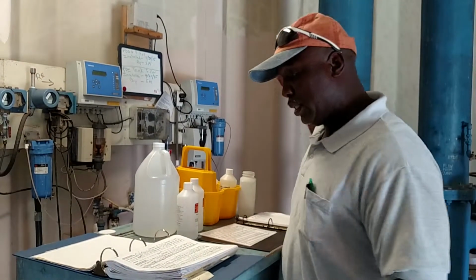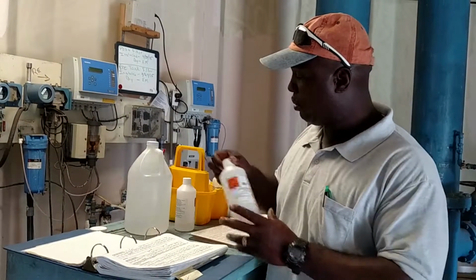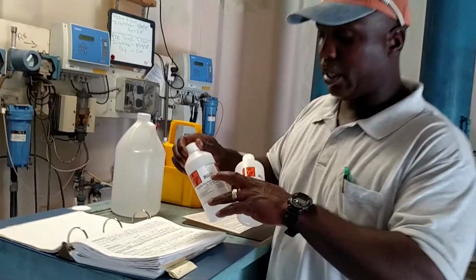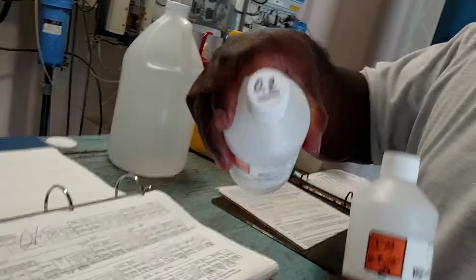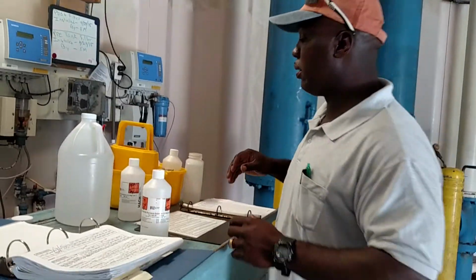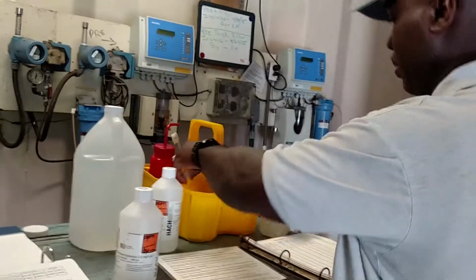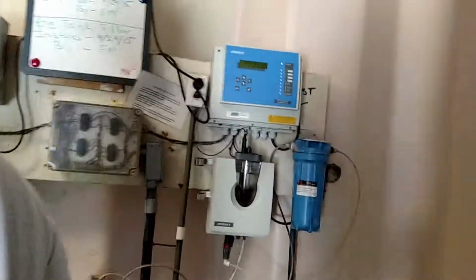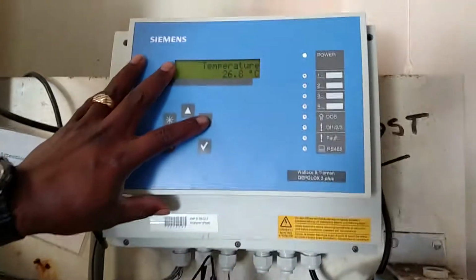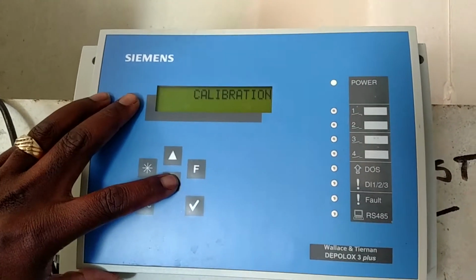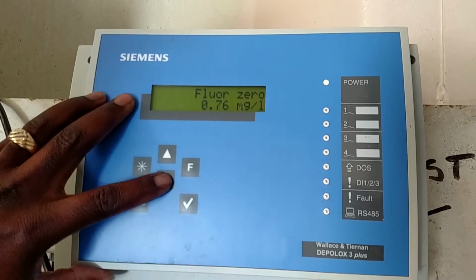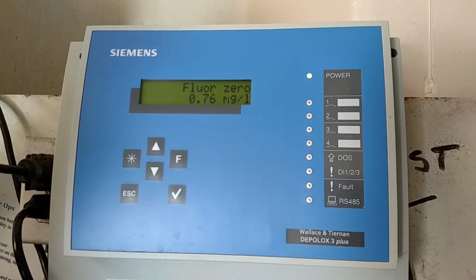Right now it's 0.76, and then I record the temperature from off of the analyzer. Then each one of my standards have a lot number on there. I record the lot number, and I record also the expiration date. And this is 0.2, so I record that there, and then I come over here to the analyzer. I got a little bottle of DI water. I hit my F to put it in calibration mode, and I go down until I get to fluoride 0. Once I get to fluoride 0, that's basically taking it out of service.